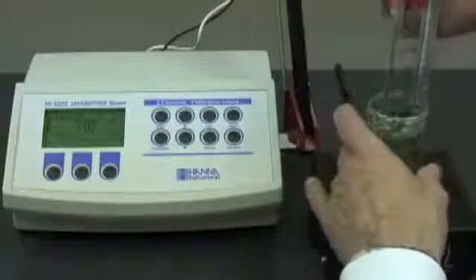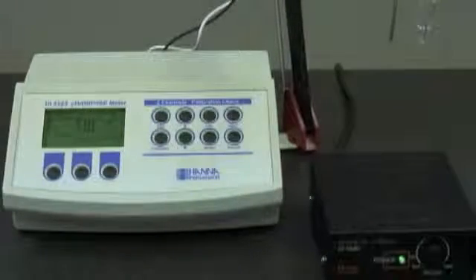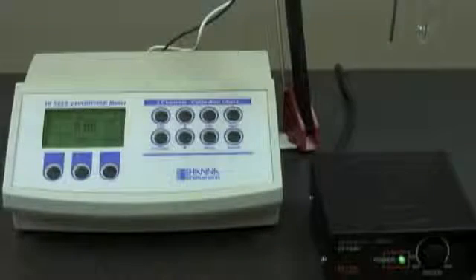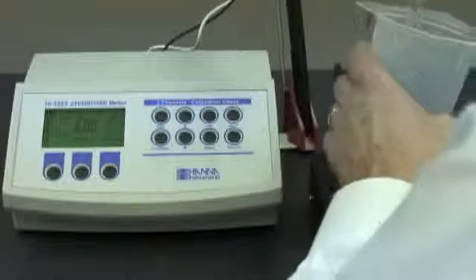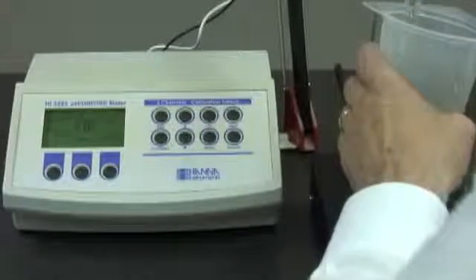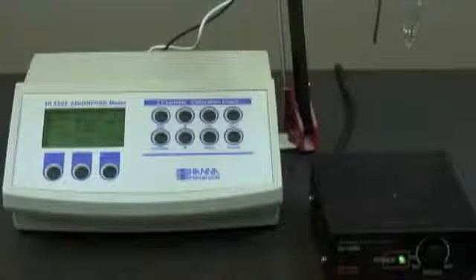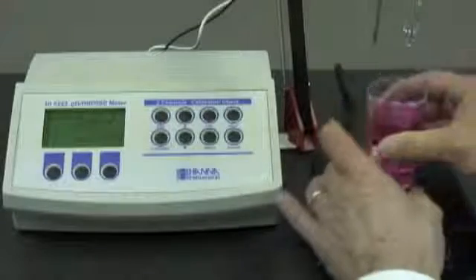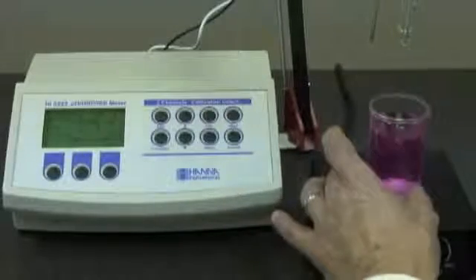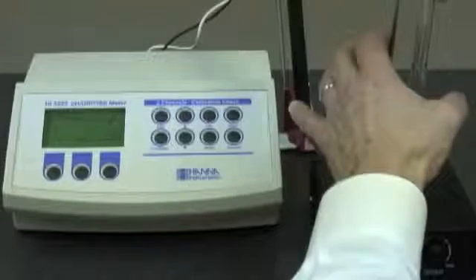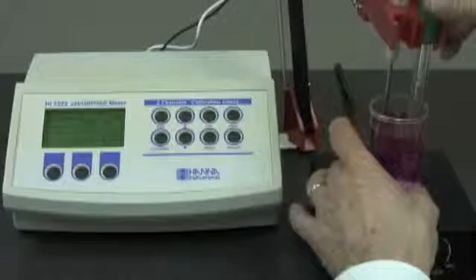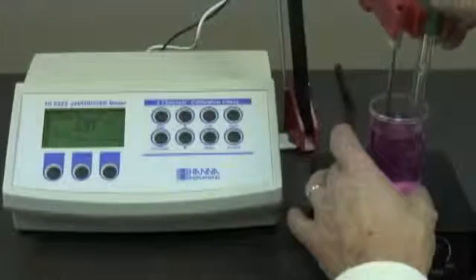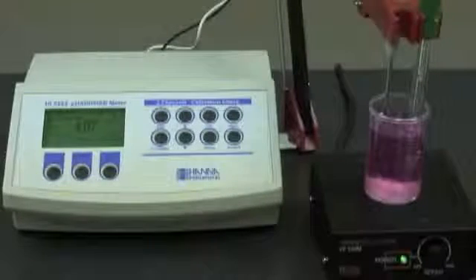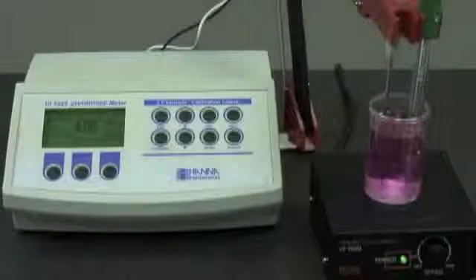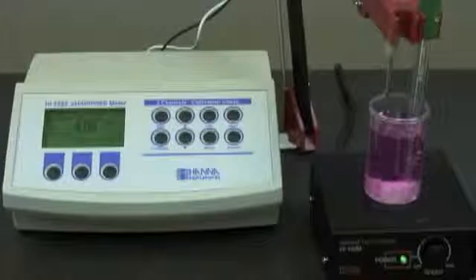And what I'm going to do next is, once again, rinse off my probe with deionized water, get any excess buffer off of there. So I've done that, and since I just happen to have a 4 with me, I'm going to put 4 onto my magnetic stir, and I'm going to put my probe in there and let it calibrate. Now at this point, if I wanted to go with a 10 or a custom buffer, then I can go ahead and do that depending on what type of calibration and how many points I want to calibrate at.